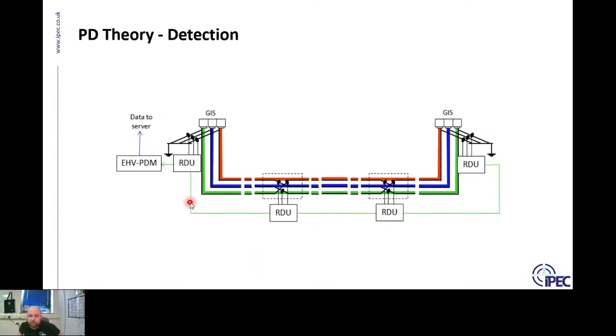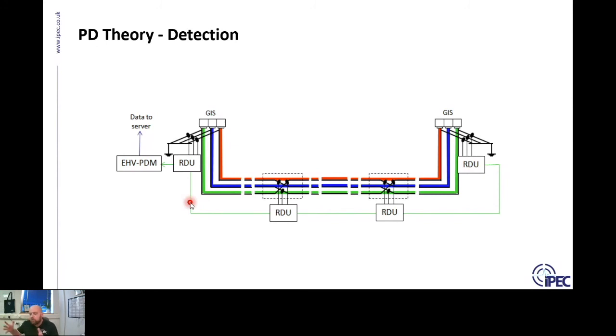In urban areas or old cables with lots of wear and tear, detection distance might be reduced. This is the same for IPEC and any other PD company — all use similar HFCTs and very sensitive data acquisition electronics. IPEC has the highest resolution of any PD monitoring device, at least for permanent monitoring solutions. But ultimately it doesn't matter what type of HFCT you're using — what matters is whether the PD signal can travel to the HFCT. All PD companies are fundamentally the same on this point.